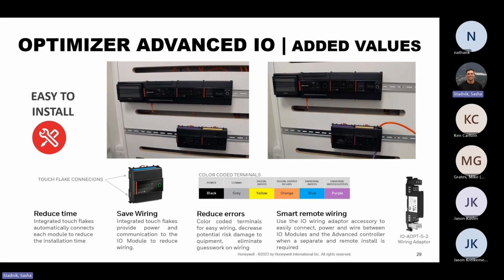This comes in handy until we have the IO that's in high demand as well, since people are asking to expand more than 4 RS-485. You can do 5, but you cannot use the IOs. Until then, 2027, we will have the IO module, likely first RS-485 Modbus, field bus, and the other, and probably BACnet MS/TP as well. So you will have that. But until then, that's the most you can do.